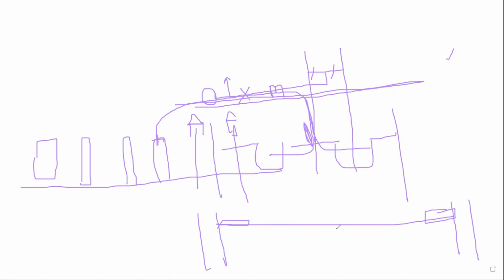The conductor will obviously not be straight, because it is a bare conductor having some tension and some weight, and it will have some sag. This sag may affect the clearances between this equipment and this one.